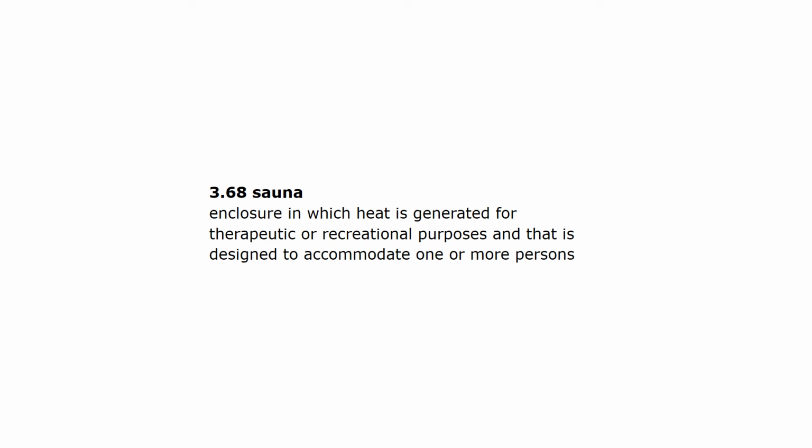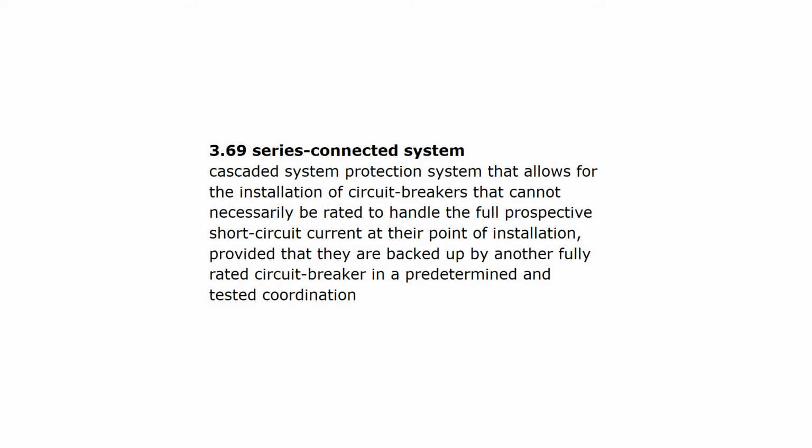Sauna: enclosure in which heat is generated for therapeutic or recreational purposes and that is designed to accommodate one or more persons. Series connected system, cascaded system: protection system that allows for the installation of circuit breakers that cannot necessarily be rated to handle the full prospective short circuit current at their point of installation, provided that they are backed up by another fully rated circuit breaker in a predetermined and tested coordination.